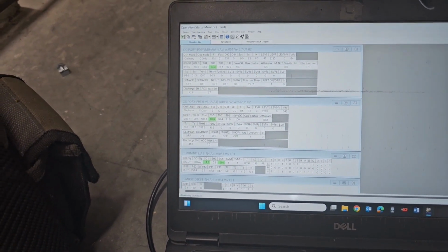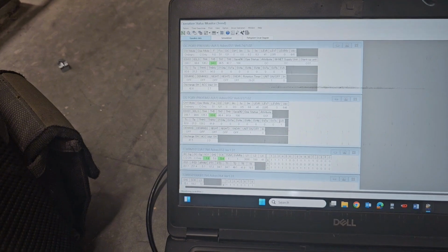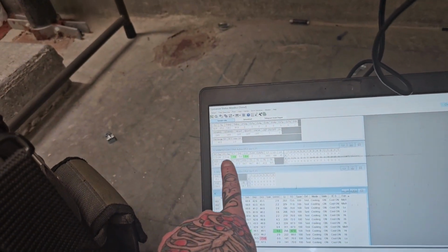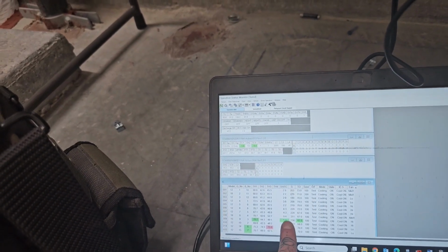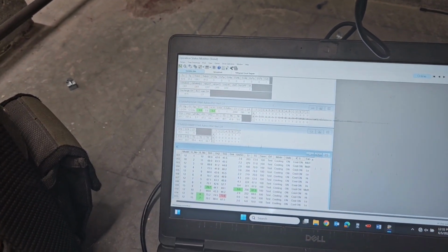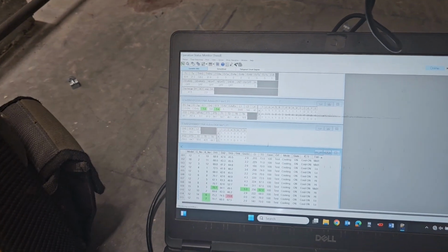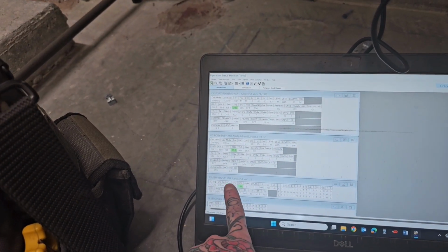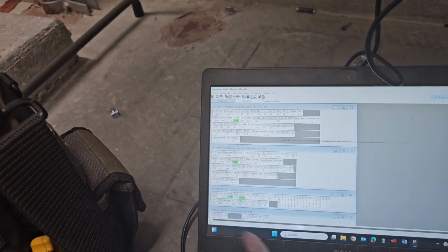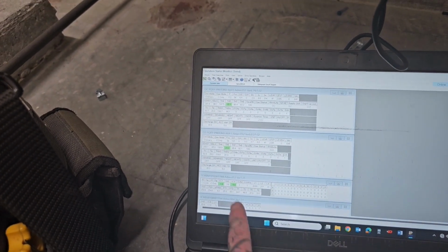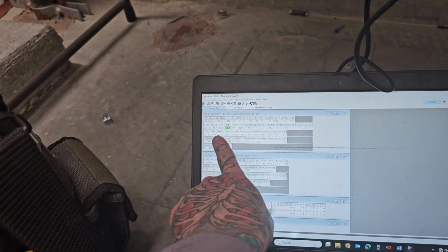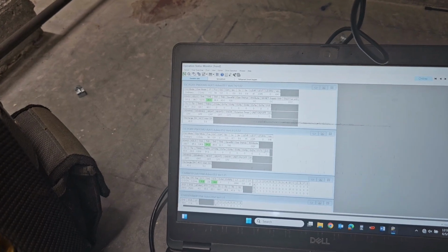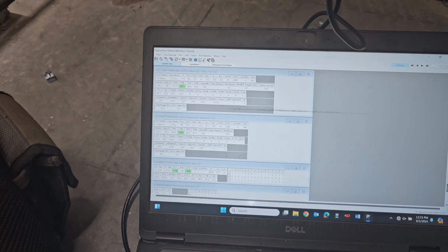So it's important to watch these for as long as you possibly can and try to confirm with yourself. Well, if you looked here and you had high superheat and low subcooling, and you had high superheat at your indoor units, and you said it was low and you started adding refrigerant, well, if it was low, then you need to prove it to yourself. You would have high superheat and low subcooling at your branch controller, but how would you explain to yourself that it's low when you have extremely low superheat at your outdoor units? You have refrigerant, it's just not in the right place. You need to figure out where it is and why it's not in the correct place.